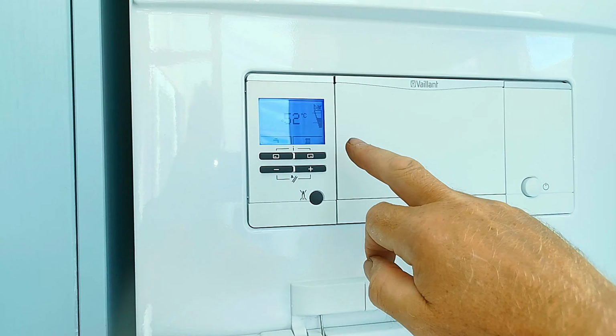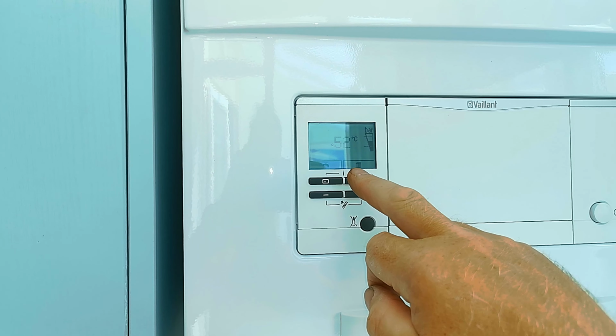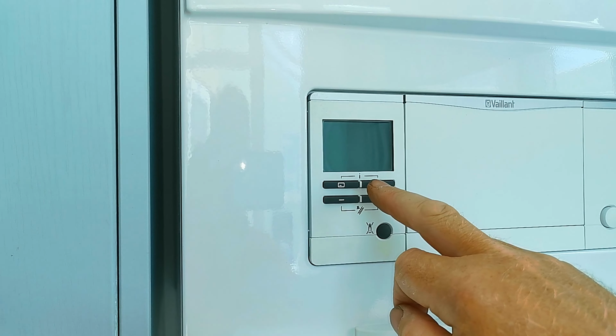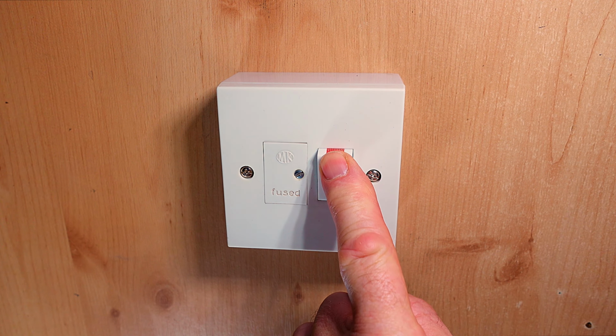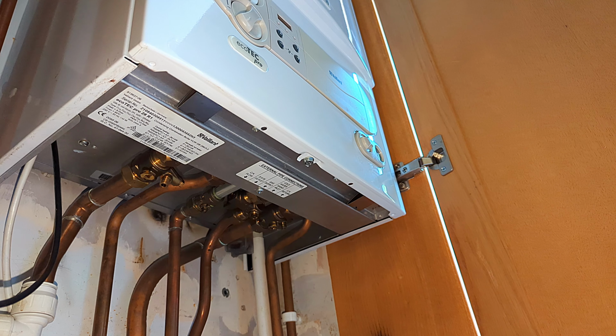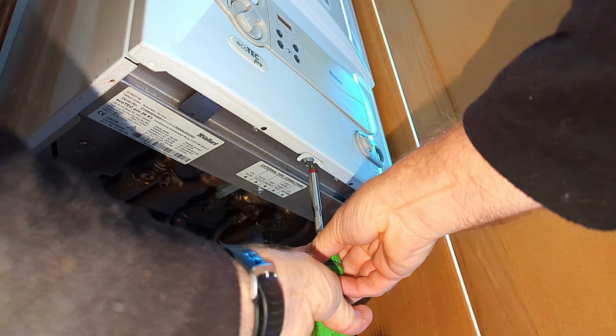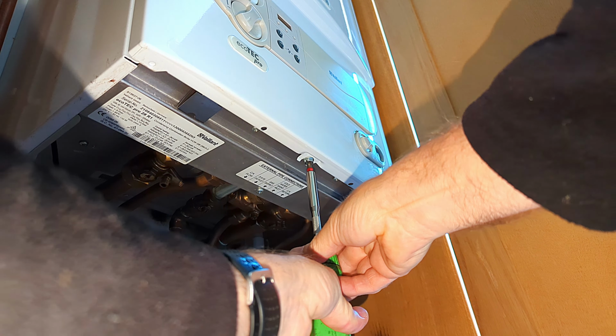Now the first thing I would do is to turn off the boiler, but because I need to get to the circuit board inside the boiler to disconnect the pump, I'll always turn off the power from outside the boiler, which should ensure there's no chance of getting any electric shocks or even damaging the boiler. I then removed the front panel by undoing the big screw in the middle and pushing up on 2 clips and lifting the front cover off.